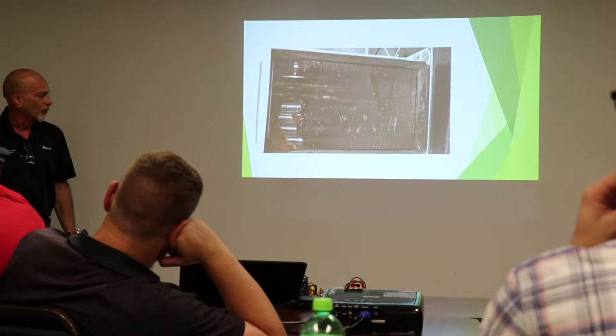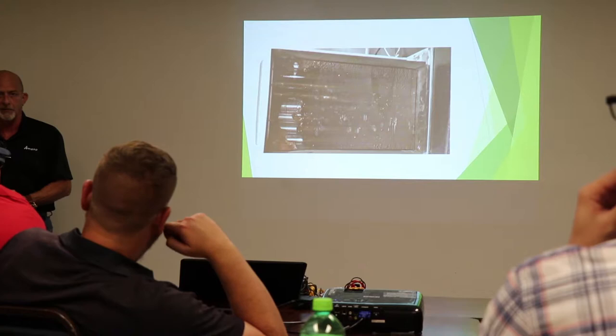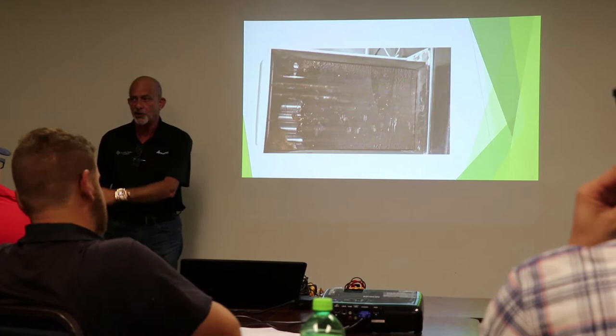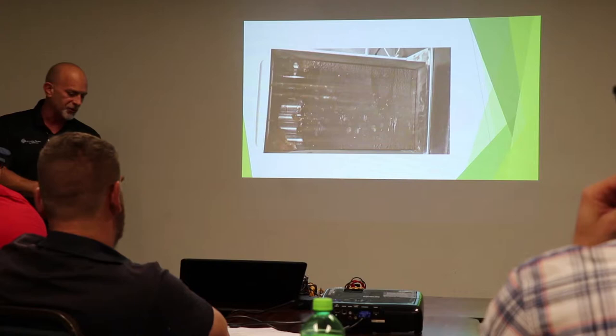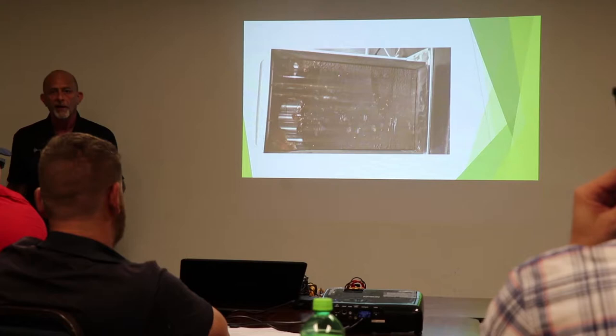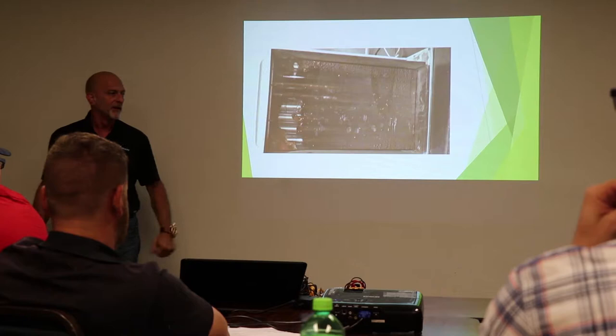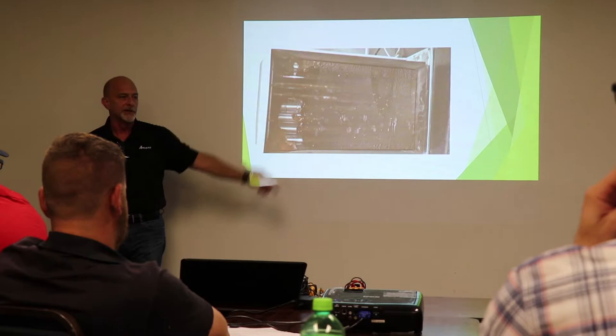So we pull our blower housing out. That's a picture of a secondary heat exchanger, right? Which is right above your blower housing. So if you're not pulling your blower housing out and inspecting everything, we wouldn't even know if our secondary heat exchanger looked like that. Now, if you've been to any of my other classes on furnace troubleshooting or air conditioning charging, whatever, we always talk about one thing, airflow. Airflow is our biggest offender in everything. You think we're going to get good airflow with a secondary looking like that? Absolutely not. So that has to be cleaned.